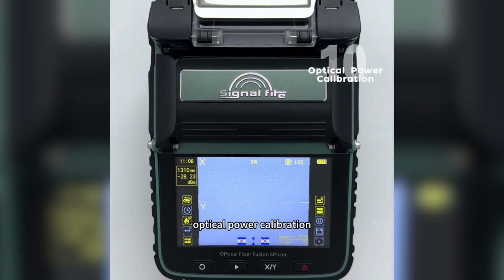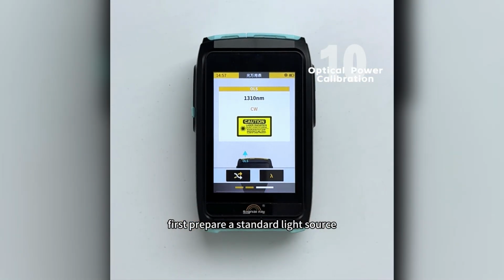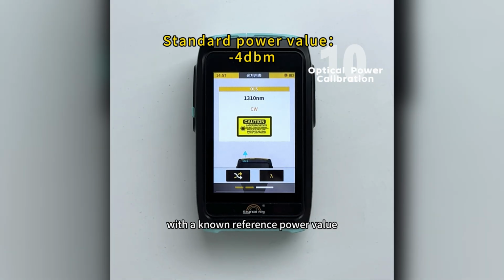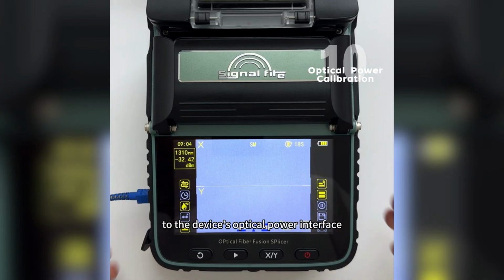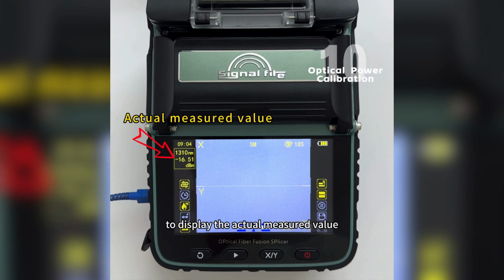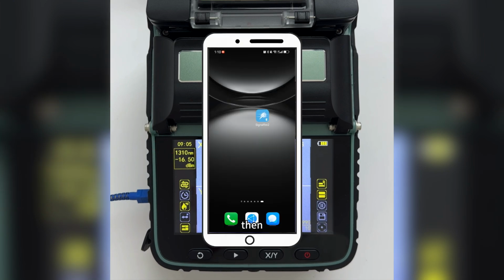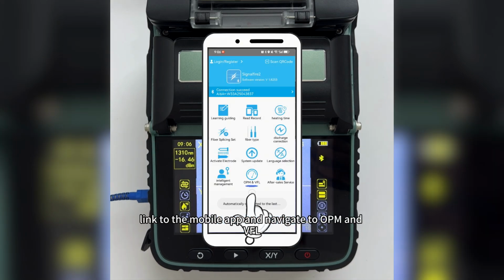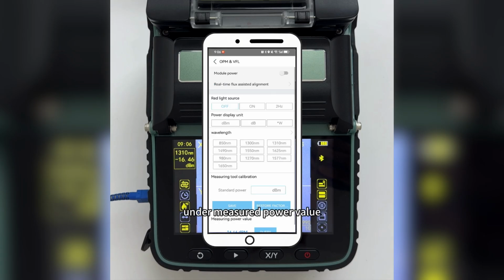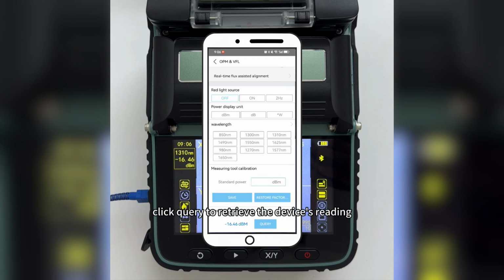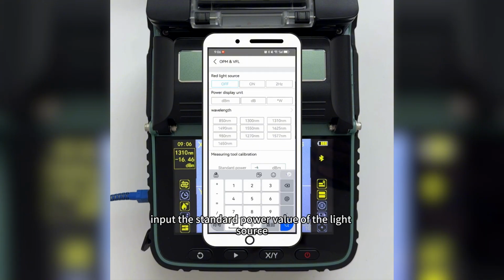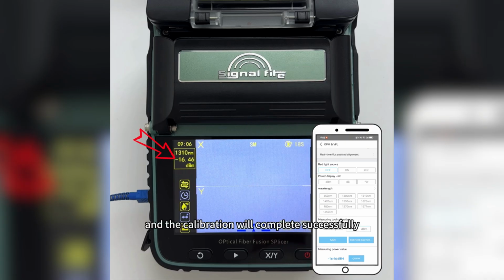Optical power calibration. First, prepare a standard light source with a known reference power value. Connect the standard signal to the device's optical power interface to display the actual measured value. Then, link to the mobile app and navigate to OPM and VFL under Measured Power Value. Click Query to retrieve the device's reading. Proceed to Measurement Tool Calibration. Input the standard power value of the light source, save the settings, and the calibration will complete successfully.